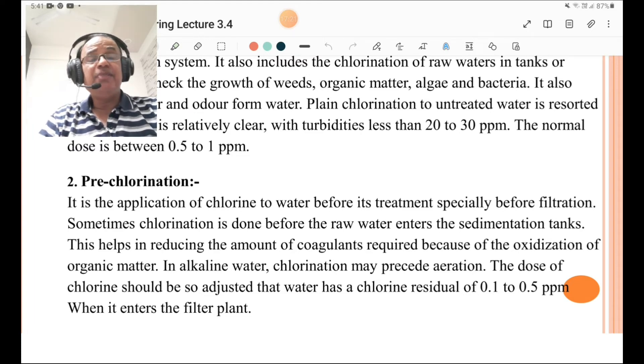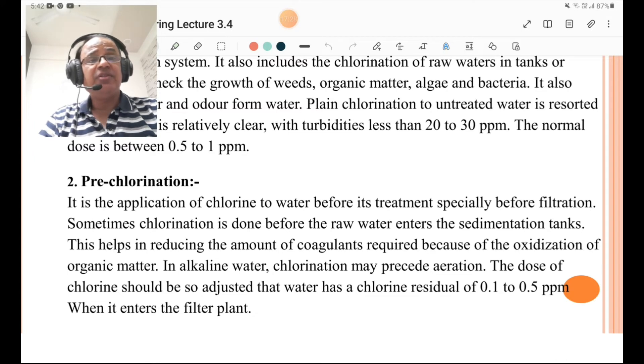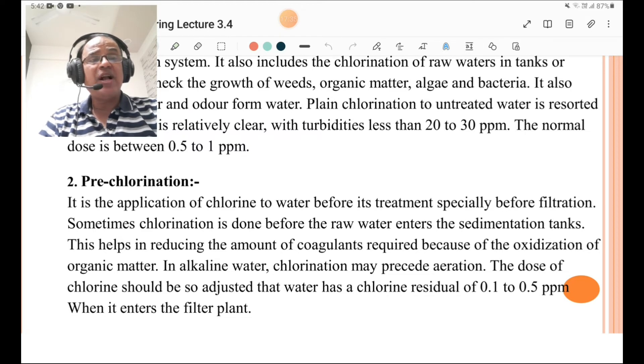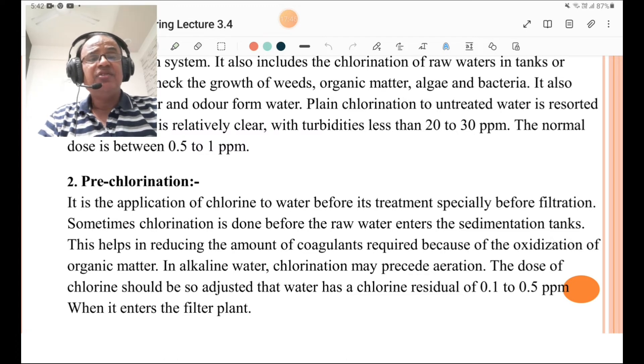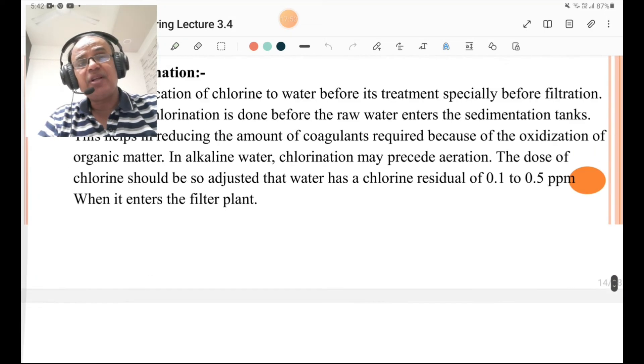Pre-chlorination is the application of chlorine to water before its treatment, especially before filtration. Sometimes chlorination is done before the raw water enters the sedimentation tank; this helps in reducing the amount of coagulant required because of the oxidation of organic matter. In alkaline water, chlorination may precede aeration. The dose of chlorine should be adjusted such that the water has a chlorine residual of 0.5 ppm when it enters the filter plant.